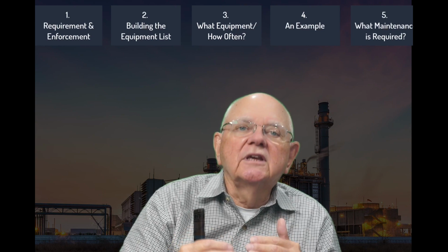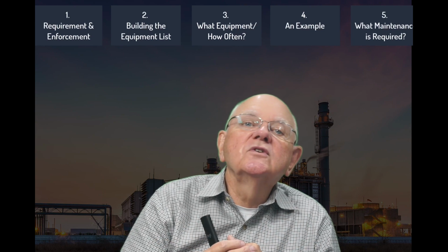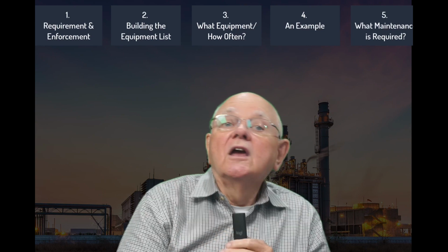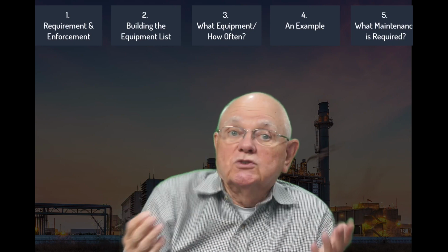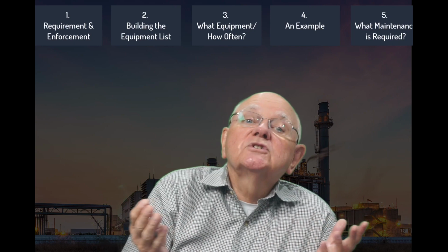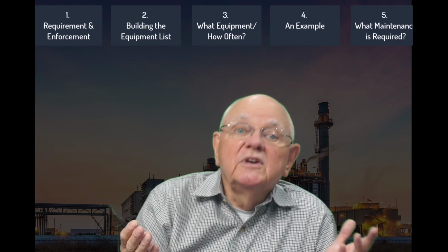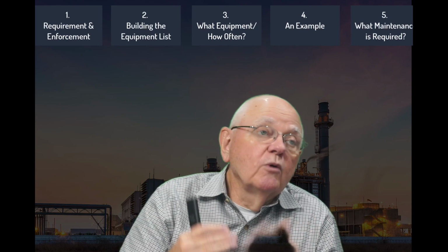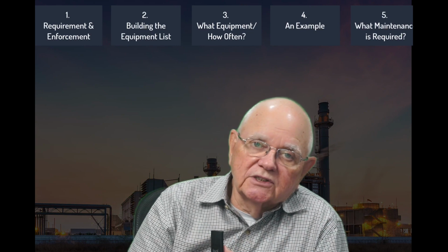So typically on the transformer, you'll be doing things like visual and mechanical inspections. What are you testing? Transformer turns ratio tests would be a very common test. Almost always we're going to do insulation resistance testing.